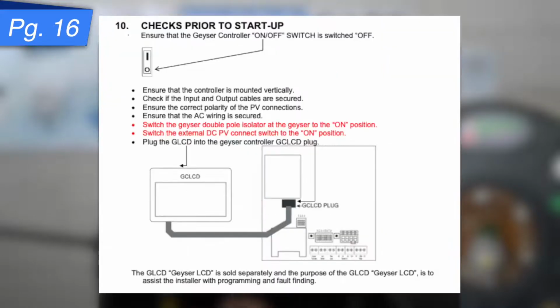I'll move over to page 16 and our checks that we are going to do now before starting up the unit. Very important. So please ensure that the geyser controller is still off at this moment, and that is with the toggle switch on the geyser controller. Again, make sure it's mounted vertically. Check that the input and output cables are secured. You shouldn't be able to move them at all. Ensure that the correct polarity of the PV connections are in place, and ensure that the AC wiring is all secured. No loose cables at this point.